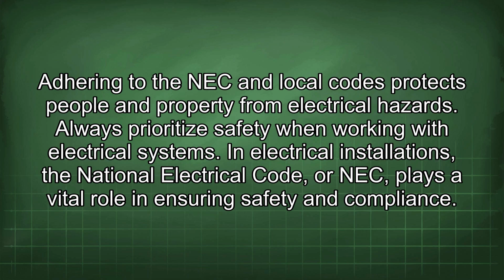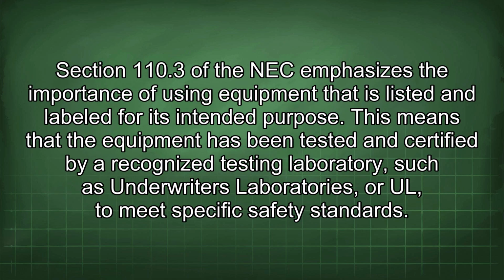In electrical installations, the National Electrical Code, or NEC, plays a vital role in ensuring safety and compliance. Section 110.3 of the NEC emphasizes the importance of using equipment that is listed and labeled for its intended purpose. This means that the equipment has been tested and certified by a recognized testing laboratory, such as Underwriters Laboratories, or UL, to meet specific safety standards.